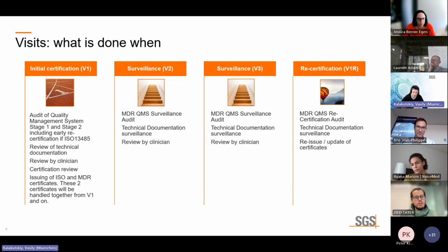So the main difference is that the MDD has its own conformity assessment procedure. So the steps for MDD are just different from MDR, though if you really zoom out, you will see the same: the quality management system and technical file in MDD, and the same in MDR, a quality management system and technical documentation. Now they call it documentation. Here we had audits and here we had audits, but the devil hides in the details.